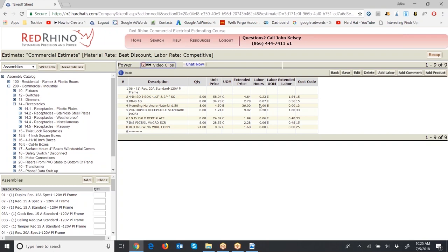Red Rhino has a labor catalog. When you input something, it inputs the labor with that material item — it pulls from the labor catalog and shows the labor hours. Eventually we'll see a report with total labor hours. The program shows 0.23 hours to install a 4S box, so for eight the extended labor is 1.84 hours. Pay attention to the unit of measure — there are basically three in Red Rhino: E for each, Roman numeral C for per hundred, and Roman numeral M for per thousand. Wire and cable is priced and labor is calculated per thousand feet.